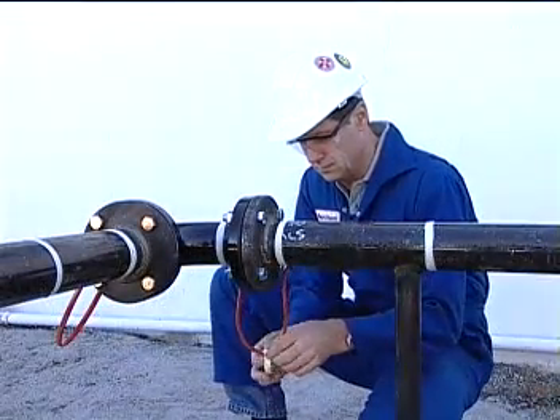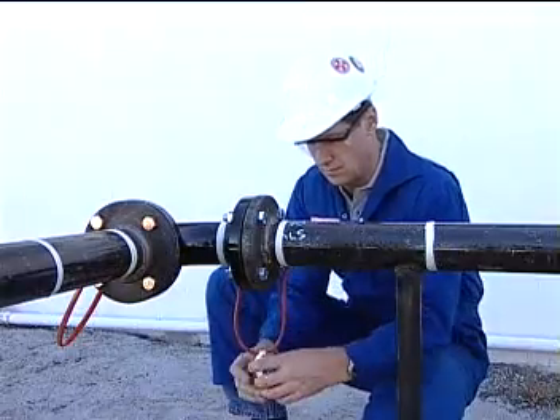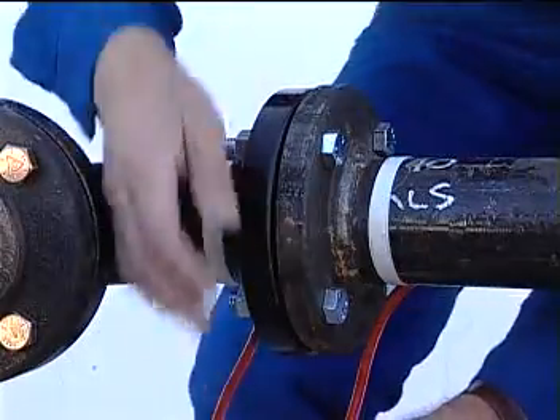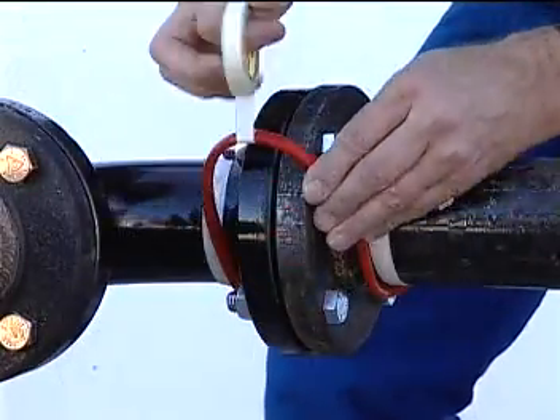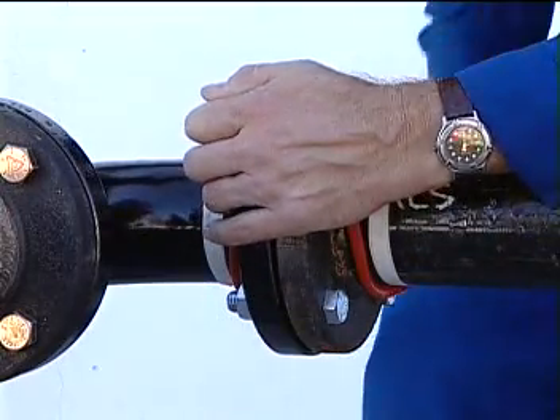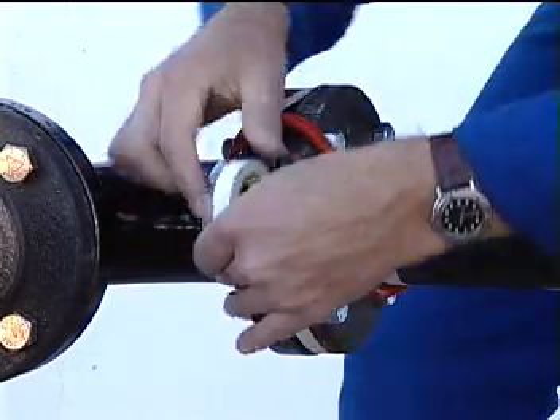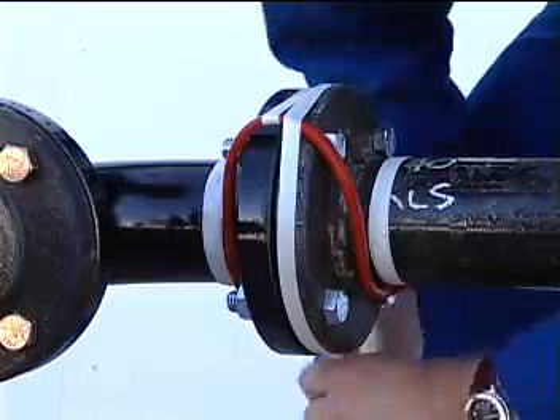The loop for flanges should be 2 times the diameter of the pipe. The extra cable used for flanges and valves not only concentrates more heat in these areas, but also allows the flange or valve to be replaced or repaired without having to cut the heating cable.